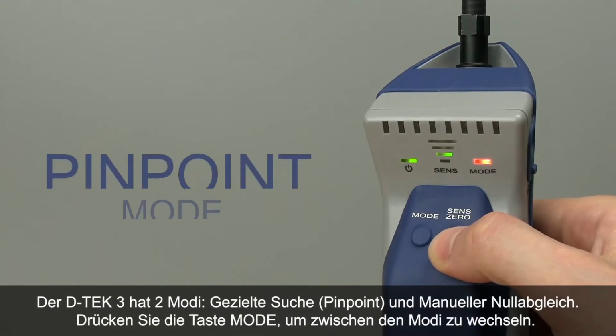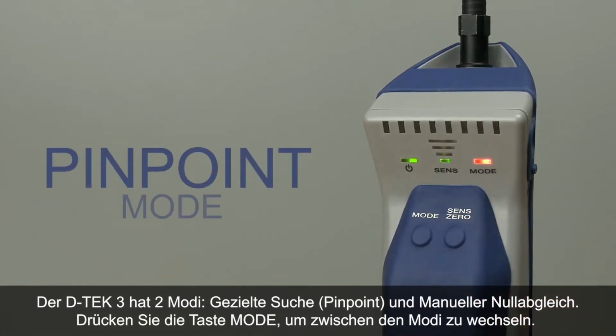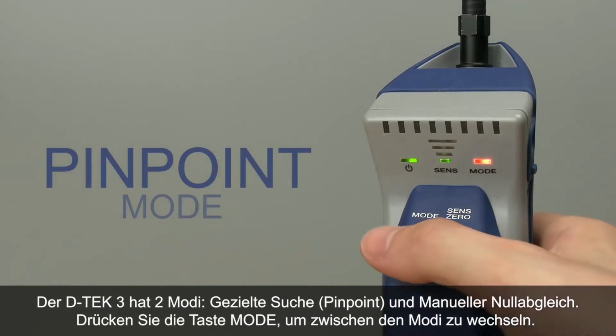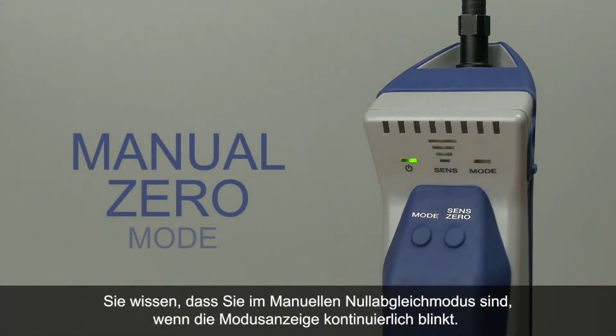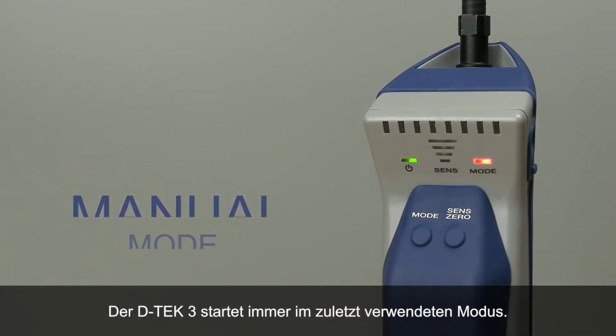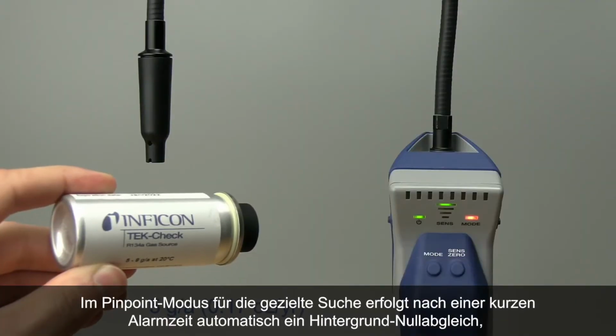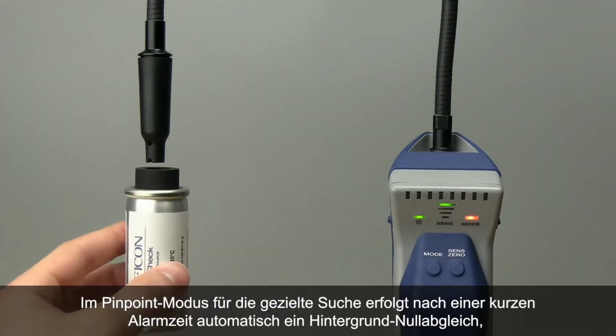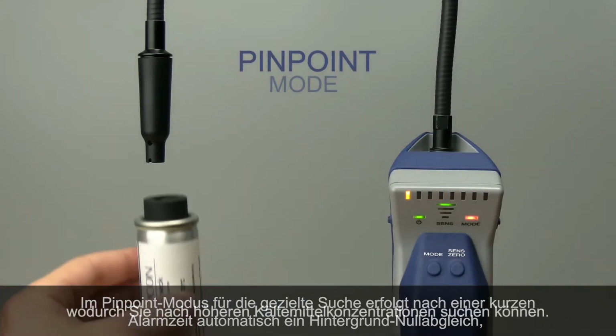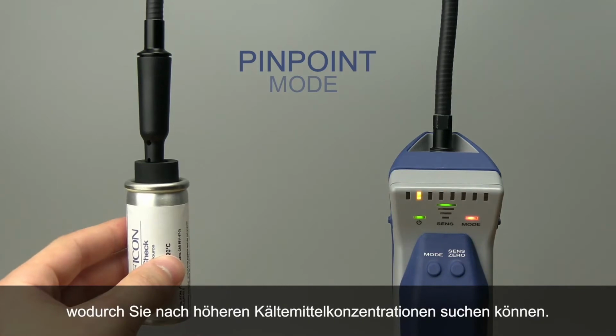D-TEK-3 has two operating modes, pinpoint and manual zero. Press the mode button to toggle between modes. You'll know you're in manual zero mode when the mode indicator flashes steadily. D-TEK-3 always starts up in the last mode that was used. Pinpoint mode automatically zeroes to the background after alarming for a short time, allowing you to search for higher levels of refrigerant.